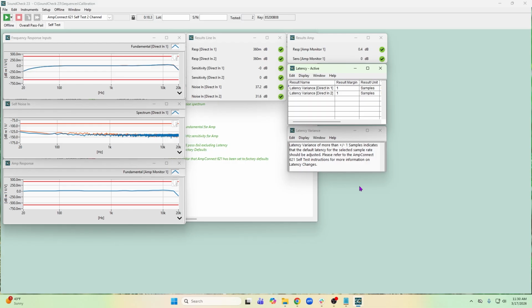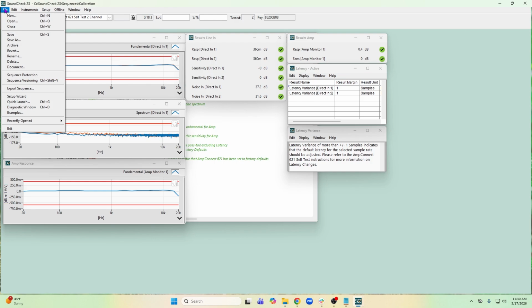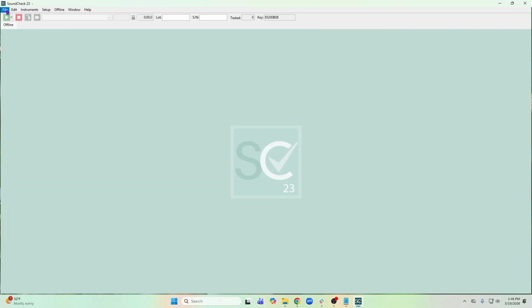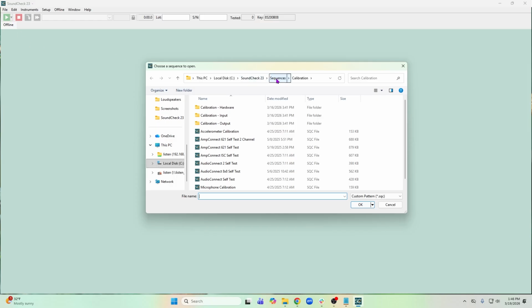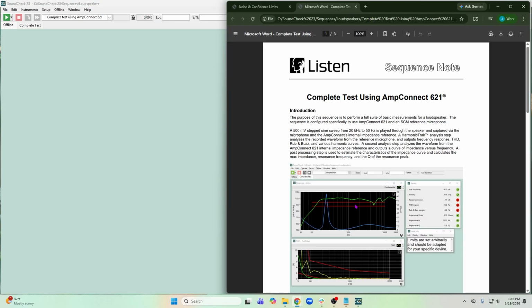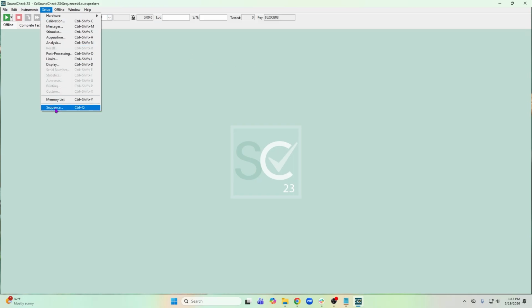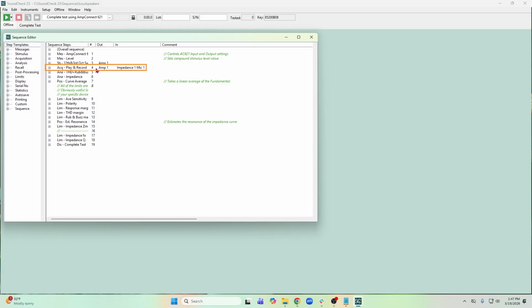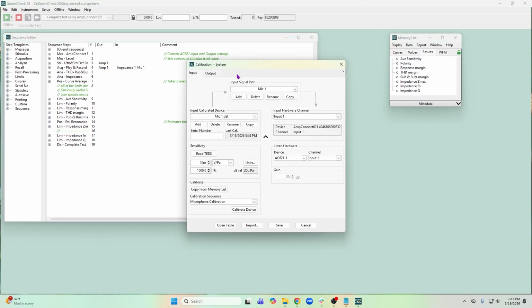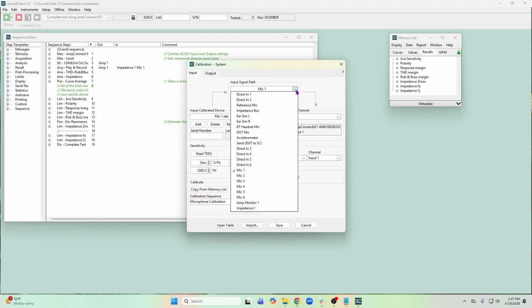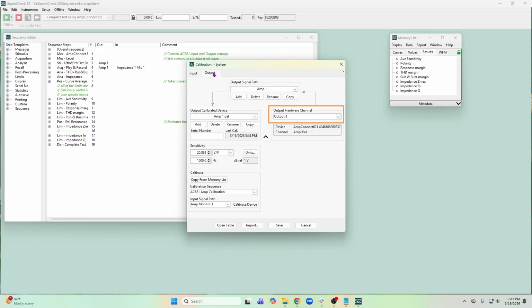SoundCheck comes with lots of pre-installed test sequences to get you up and running quickly. Let's open up the complete test using AmpConnect 621 sequence from the loudspeakers folder. You can see there's an instructions document here if you want to learn more about the test. Before we run the sequence, let's double check our routing and signal paths. We can see here in the sequence editor that the acquisition step uses mic 1, amp 1, and impedance 1 as our signal paths. SoundCheck automatically created these in signal paths and calibration, and we can see here they're automatically set to the appropriate hardware channel.